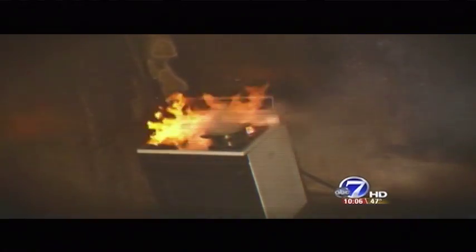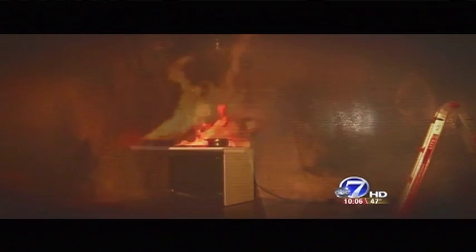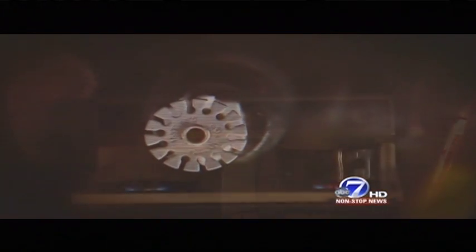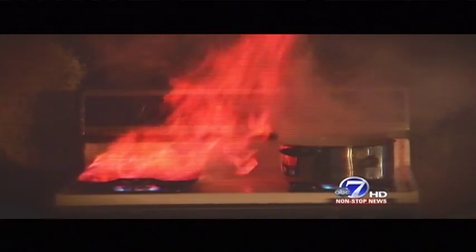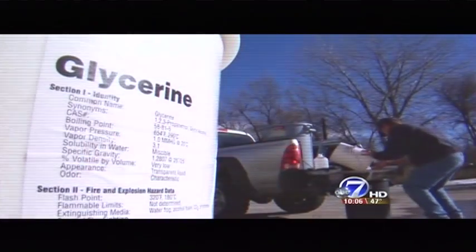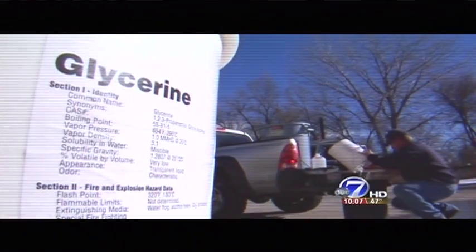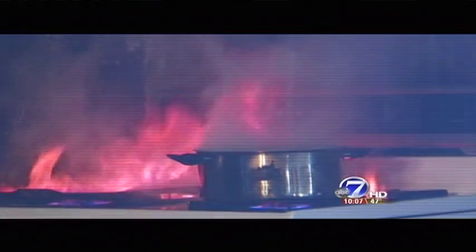Our investigation showed how high concentrations of antifreeze in fire sprinkler systems can act not as a fire suppressant but as a fire accelerant. Our test was based on circumstances where investigators determined antifreeze containing either glycerin or propylene glycol can ignite when it hits a hot surface.